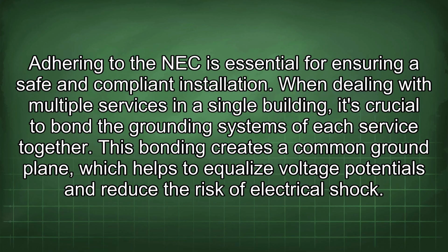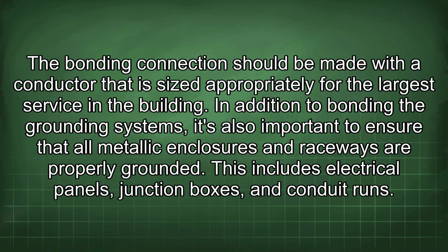When dealing with multiple services in a single building, it's crucial to bond the grounding systems of each service together. This bonding creates a common ground plane, which helps to equalize voltage potentials and reduce the risk of electrical shock. The bonding connection should be made with a conductor that is sized appropriately for the largest service in the building.